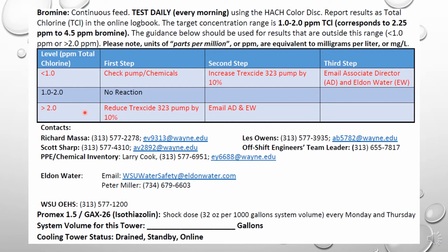So if you get less than 1 part per million at a standard program tower, you're going to check your pump and chemicals and you increase your Trexide by 10%. Don't forget to email your associate director and Eldon Water, and you want to make sure you also record it in your online logbook. Document, document, document. If it's high, if it's greater than 2, you reduce your pump. Same thing, email associate director, Eldon Water, and document it in the online logbook.